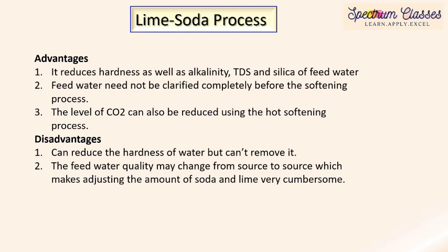The advantages of the lime soda process are: it reduces hardness as well as alkalinity; it reduces total dissolved solids and silica in feed water; the raw water does not need to be clarified before softening; and the hot process can also reduce dissolved CO₂. The disadvantages are: it can reduce but not completely remove hardness; and feed water quality varies by source, making it difficult to accurately adjust the amounts of lime and soda required. The next video will cover calculations and numericals.